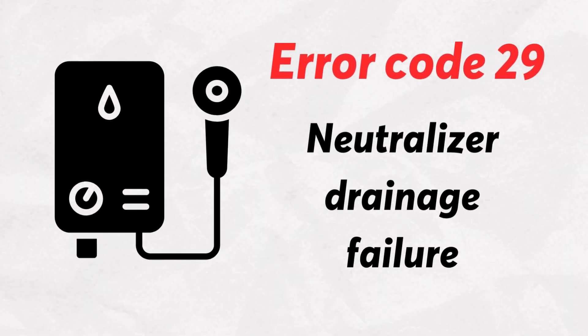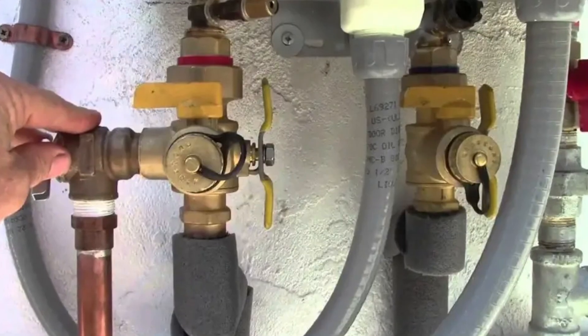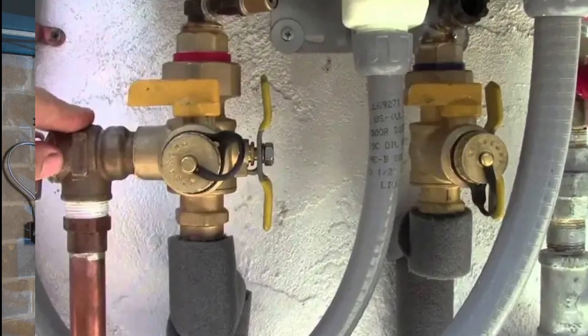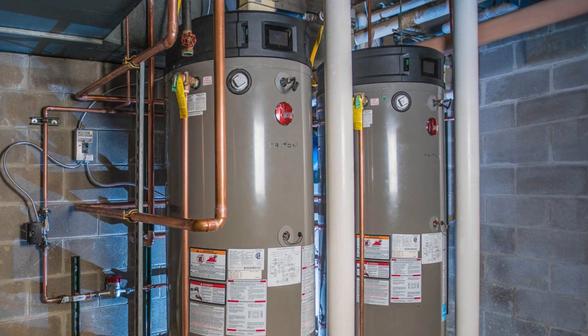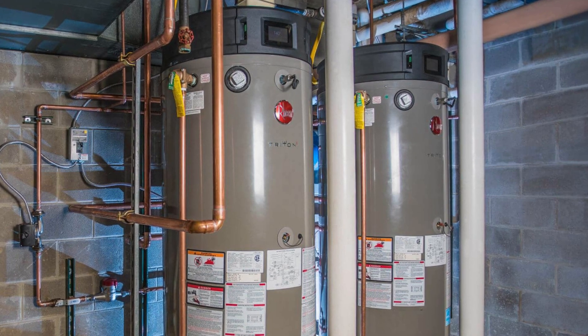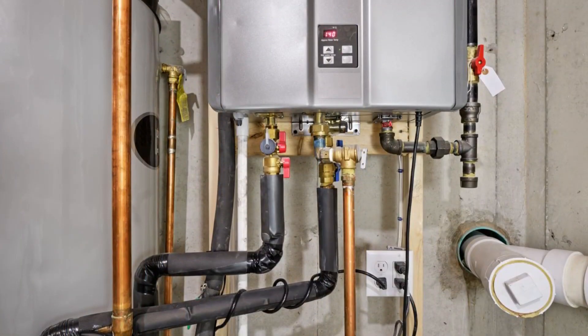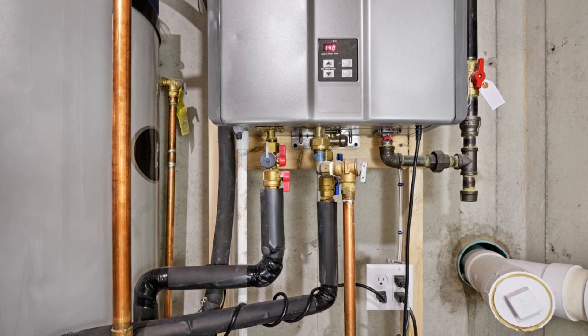Rheem Tankless Water Heater Code 29 is an error code that indicates a neutralizer drainage failure. The error code indicates that the neutralizer or drain is clogged up. The neutralizer's main function is to drain condensate away from the heater. The unit flashes the 29 error code once the neutralizer and drain are blocked up, to prevent flooding in the burner.